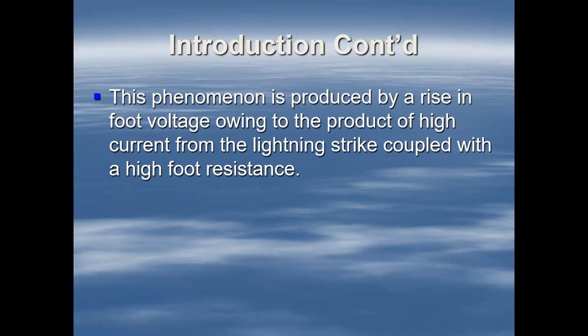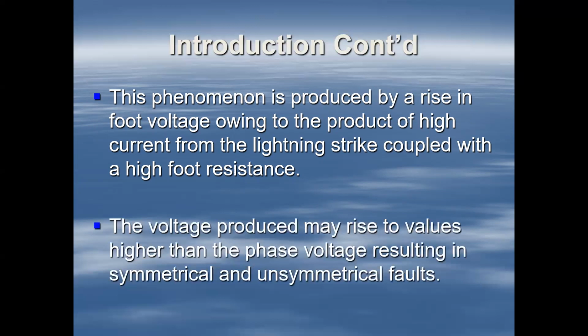Of course, we know that ideally the potential at earth would be zero. But under these circumstances, with high resistance and that lightning strike, you can get several kilovolts at your foot resistance. And if that becomes larger than your phase voltage, given the difference in potential, with the higher potential coming from the foot resistance, then you have current flowing into the network from the lightning strike.